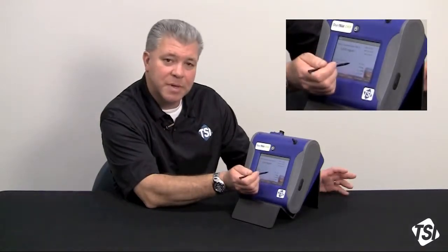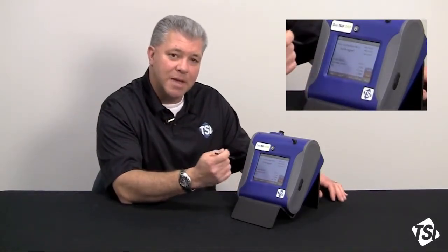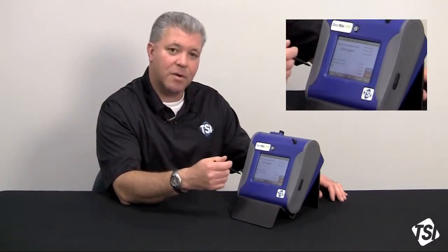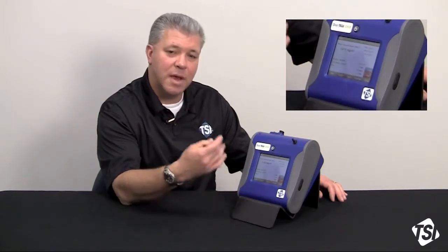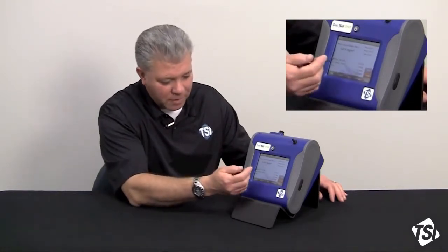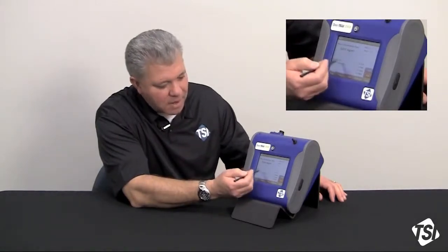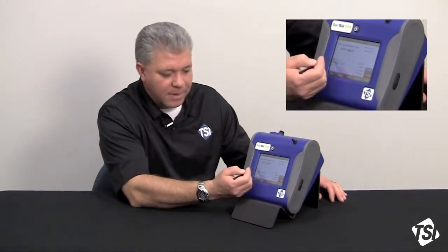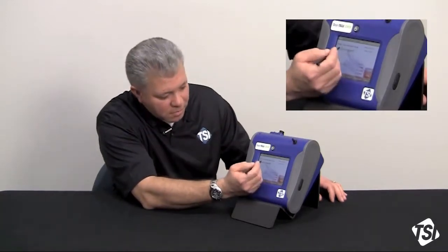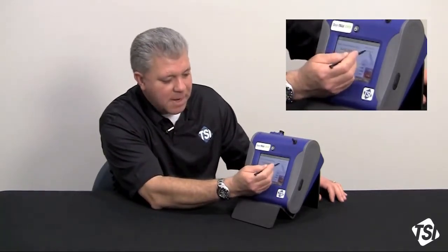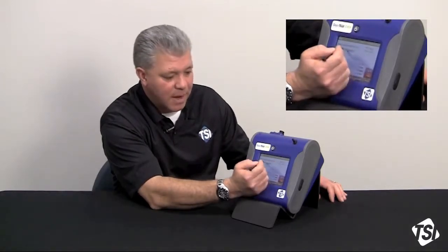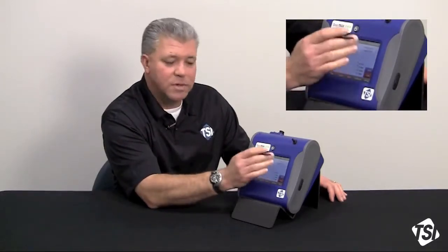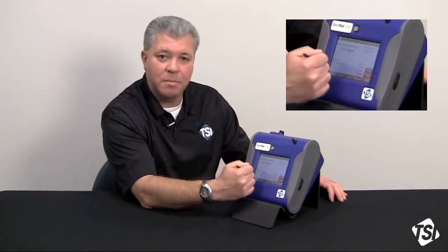Notice that respirable is missing. Respirable is not typically a size fraction that's looked at in indoor air quality or outdoor fugitive emissions monitoring. Typically the PM fractions and total fractions are looked at for sizing convention. If I toggle that again, I now have the IH mode. So we've got respirable, we've got total, and PM10 thoracic. So you've got your total dust, you've got thoracic and respirable size fractions. Notice that PM2.5 and PM1 are missing.